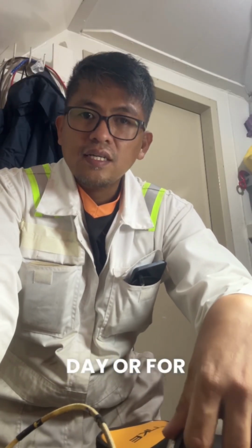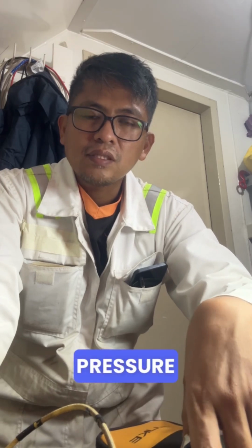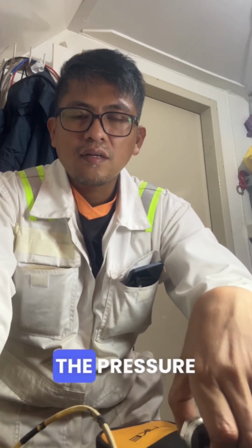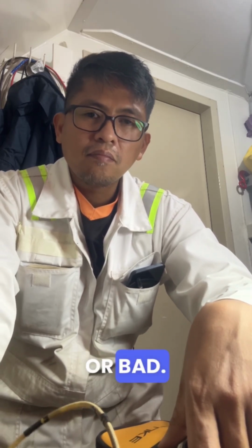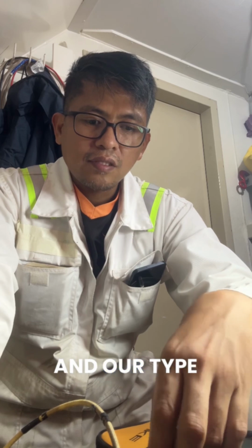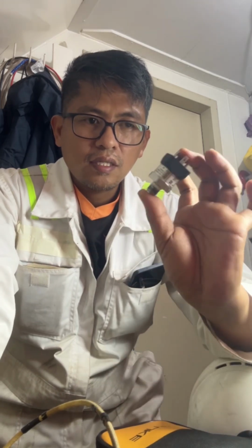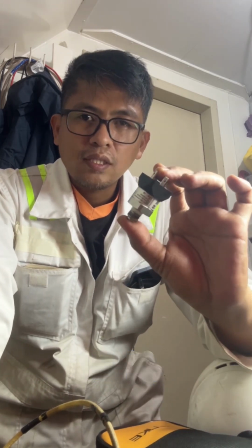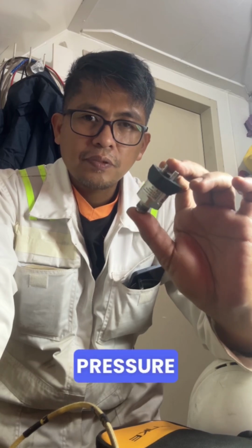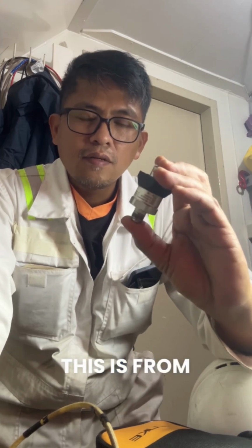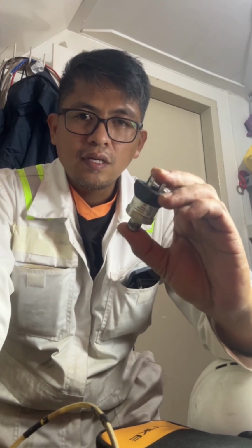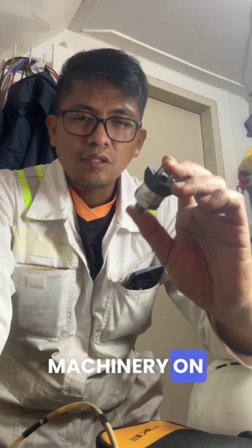And for this video, our topic is about pressure sensor. I'm going to demonstrate how to check the pressure sensor, if the sensor is still good or bad. Our type of sensor is this one. This is a 4 to 20 milliamp loop powered pressure transmitter. This is from one of our equipment, or machinery, onboard.